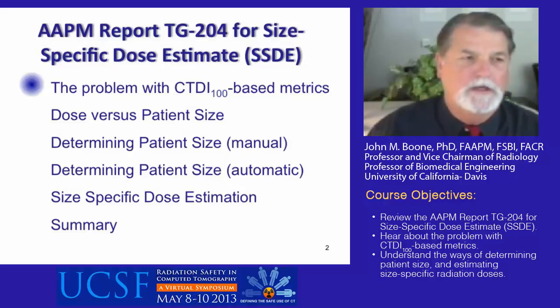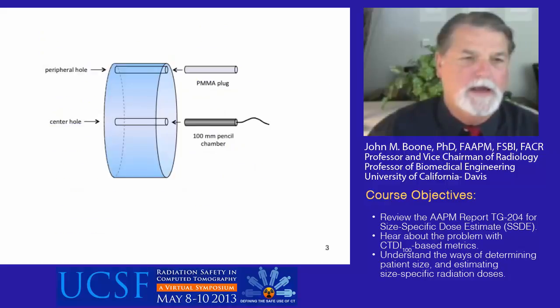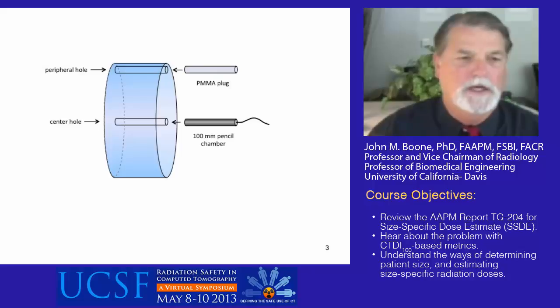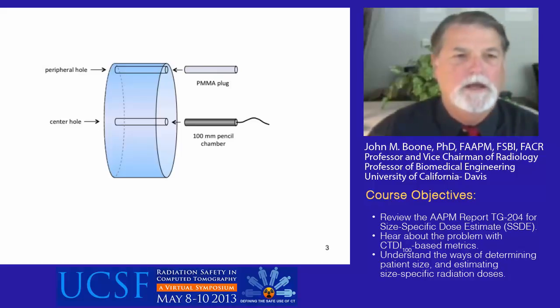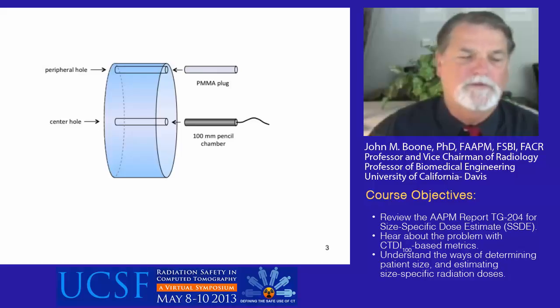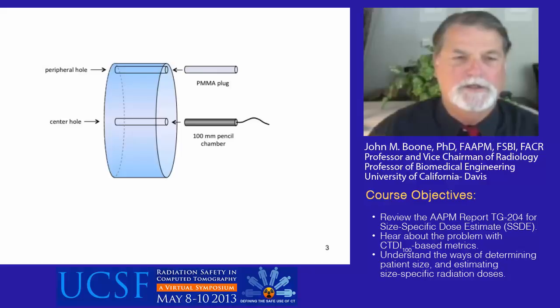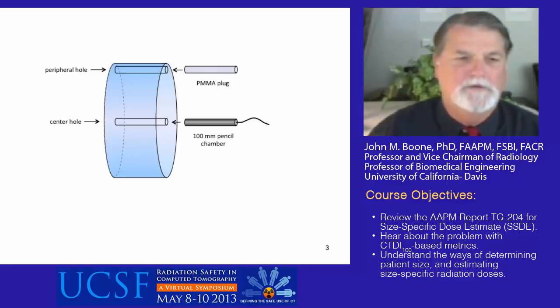Slide three shows the standard apparatus used for measuring CTDI sub-100, which leads to the computation of CTDI vol, displayed on the scanner console. You use a 100-millimeter pencil chamber, insert it in the center hole or peripheral hole, do an axial CT scan and make measurements. A one-third, two-third weighting of these values gives CTDI-W, and essentially CTDI vol for a pitch of one as well.